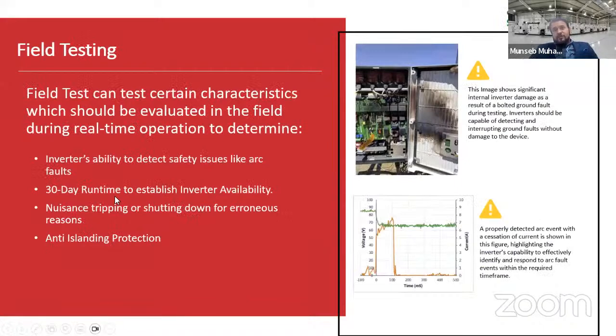Then you further move down to the field test in order to evaluate the real-time operation and the durability of an inverter when it is exposed to different on-site faults like arc faults, grounding faults. So it tells more about the inverter's ability to detect safety issues like arc fault. For example, on the right, you see this inverter got burned. Actually, it failed to protect itself from a ground fault arcing on the side.